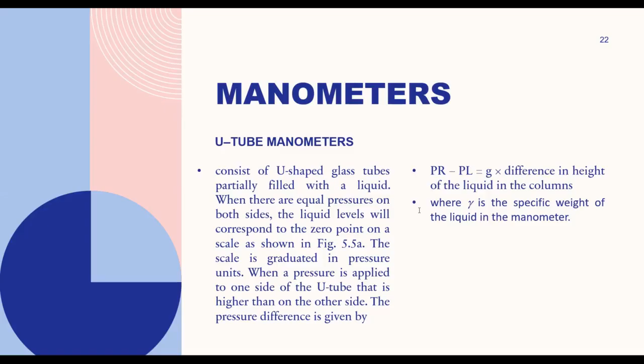When there are equal pressures on both sides, the liquid levels will correspond to the 0 point. The scale is graduated in pressure units. When a pressure is applied to one side of the U-tube that is higher than the other side, the liquid rises in the lowered pressure side, so that the difference in the heights of the two columns of liquid compensates for the difference in pressure. The pressure difference is given by P_R - P_L = γ times the difference in height of the liquid in the columns, where gamma is the specific weight of the liquid in the manometer.